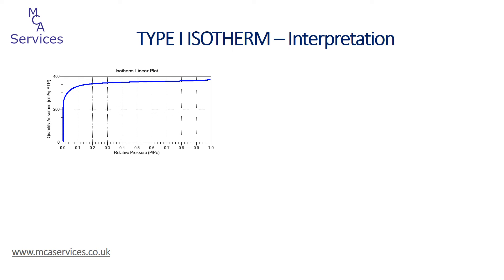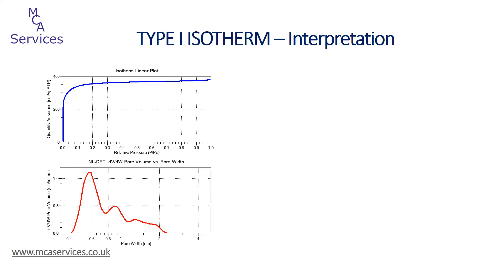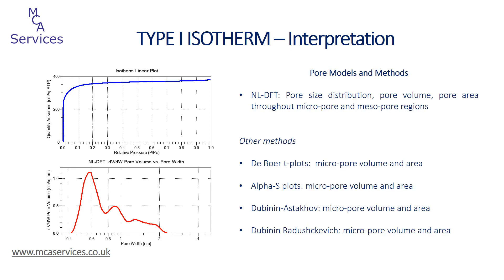Equilibration intervals are typically 30 to 45 seconds in this region. This is very demanding on instrument engineering, and today we do have instruments capable of acquiring really high quality adsorption isotherms in the micropore region. We have a number of tools at our disposal for converting these into pore size, pore volume, and pore area data. Density functional theory — DFT, or more specifically non-localised DFT — is a very powerful tool in this respect and is now frequently our go-to method. This is the NLDFT differential pore size distribution plot generated from the above isotherm, from which we can also calculate the corresponding pore volume and micropore area contribution.